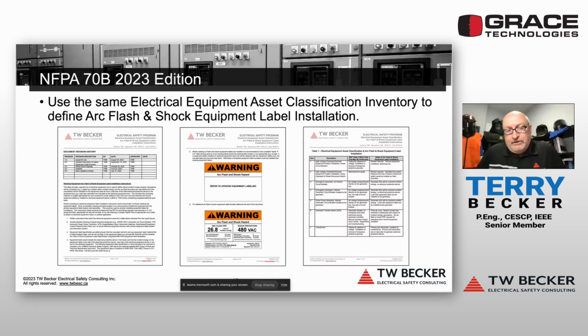For arc flash hazard and energy analysis studies, I've always told clients you need to get an electrical equipment asset list, and define where work will be completed at that asset. Then we need an incident energy calculation, so you can get a better quote on the actual cost to do that study, or a more definitive bus count and/or equipment label count at the end of the day.